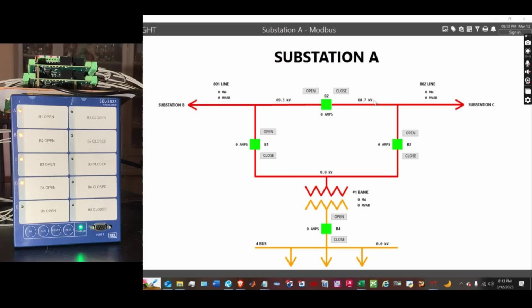Looking at the display and the breaker simulator front panel, we can see that all 4 breakers B1 through B4, are open. This is shown on the SCADA screen as a green color of the breaker. The incoming line voltages, which are the voltages displayed on the bus segments connected to the 801 and 802 lines in the upper left and right of the screen, are shown as 69.3 and 68.7 kV respectively.